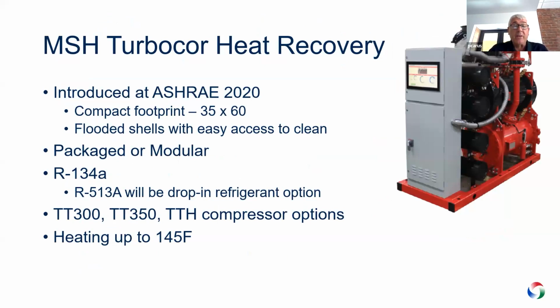Can do it in either a packaged or a modular version, but if you look closely, notice that behind the control panel, there are 4 headers there. So it is truly a modular machine. Comes in 90, 120, and 140 size modules. Again, up to 14 banks. Typical application for heat recovery, you're going to be able to do 100, 200, 300 tons of heat recovery. Currently today, 134A, but 513A is also available, and 513A and 134 are very, very similar in terms of their performance.